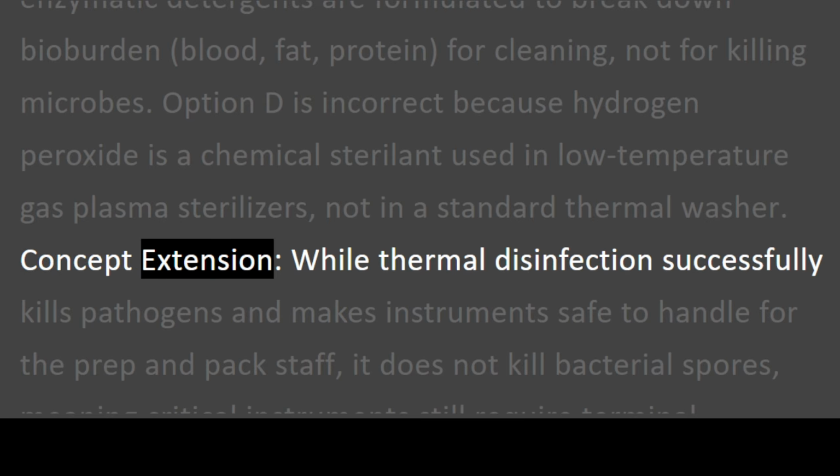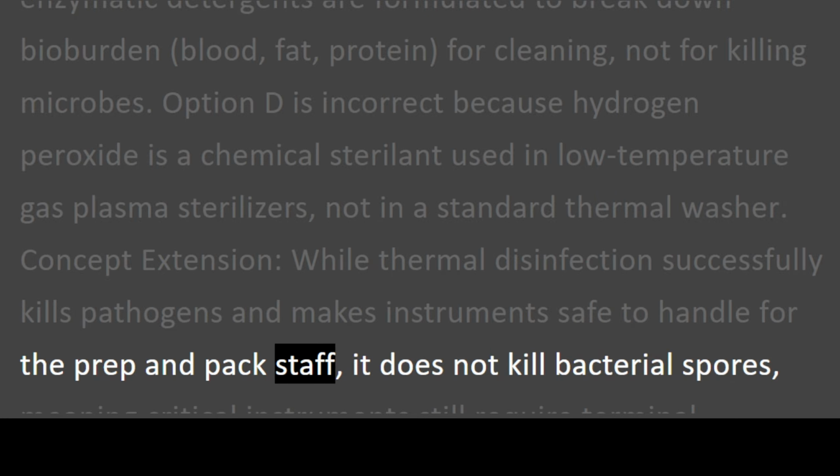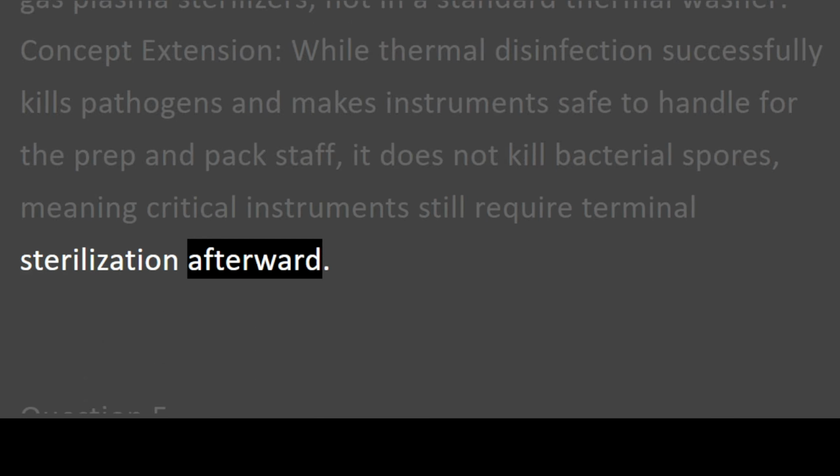Concept extension. While thermal disinfection successfully kills pathogens and makes instruments safe to handle for the prep and pack staff, it does not kill bacterial spores, meaning critical instruments still require terminal sterilization afterward.